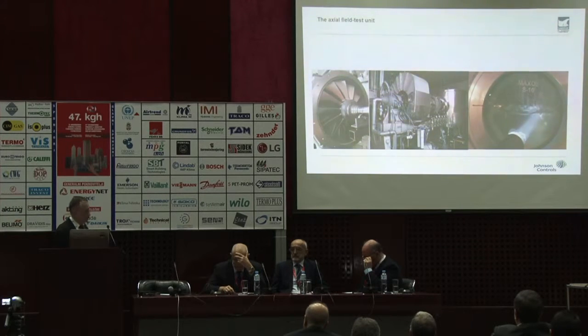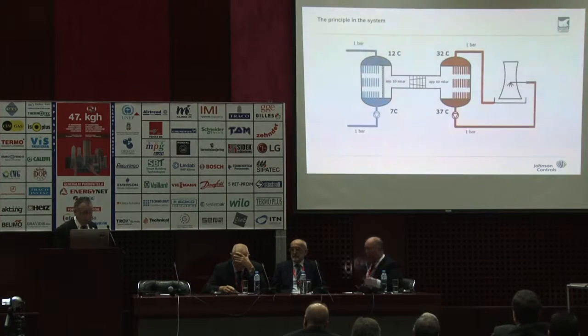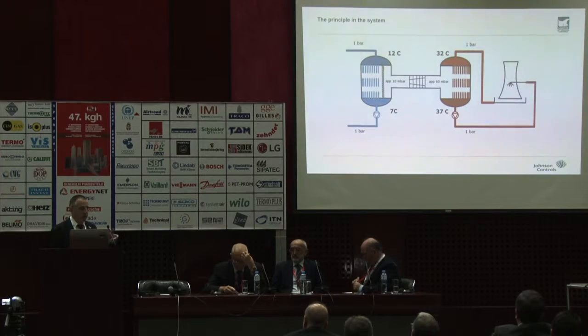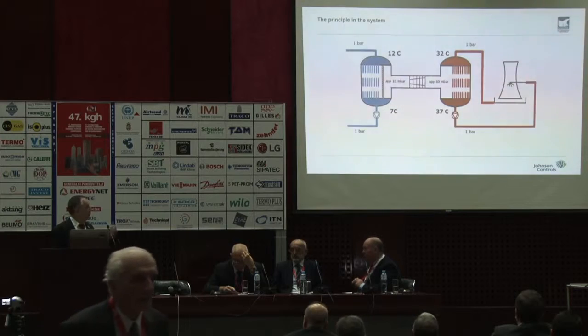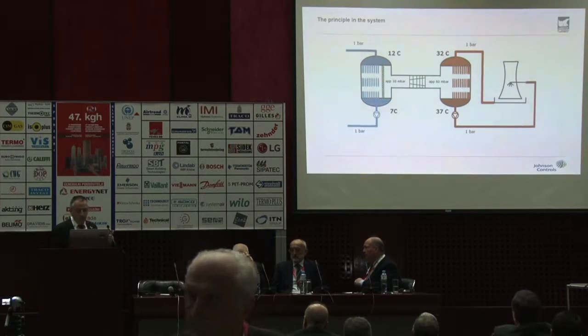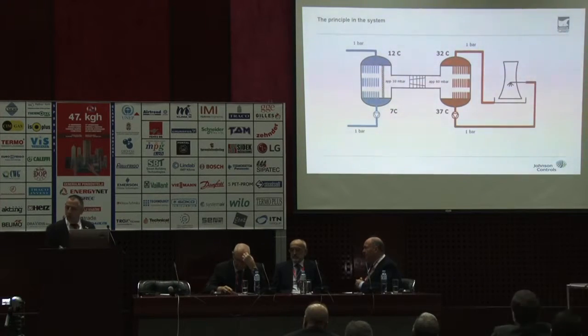shows the boiling, but actually the boiling happens inside in a falling film thing, a little bit like this, where the water falls down, and about 1% evaporates to cool down the rest of the water. 1% means a lot of volume because of water vapor, but it's not very much water. The trick is also here, normally when you have a refrigeration system and a cooling tower, you always add water into the cooling tower. But in this case, you will have to add it on the low side of the system because you are evaporating and going out.